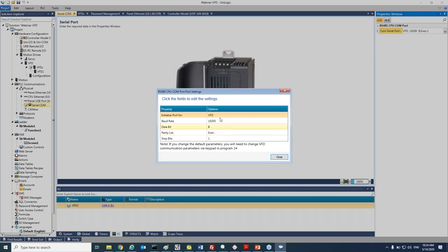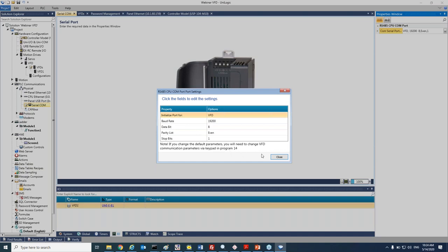Here are the default parameters. Each time you take the VFD out of the box, these will be the default parameters. So baud rate will be 19200 and parity check will be 8, even, 1. As Ophir mentioned, we can change those parameters via group 14.